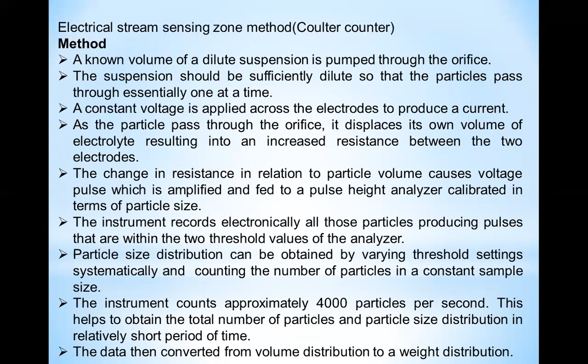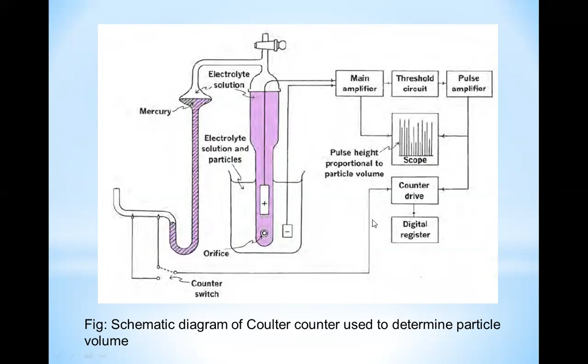So this is the schematic diagram of the counter apparatus used to determine particle volume. Here, electrolyte solution is placed with the particles of which we are going to determine the particle volume. This is the orifice, either side of which electrodes are placed. When the powder particle passes through this orifice, it displaces its own volume of the electrolyte solution, and this is then observed by the main amplifier, then the pulse amplifier, and a pulse height proportional to particle volume is determined.